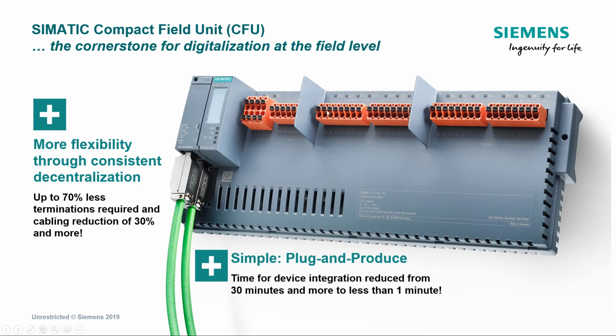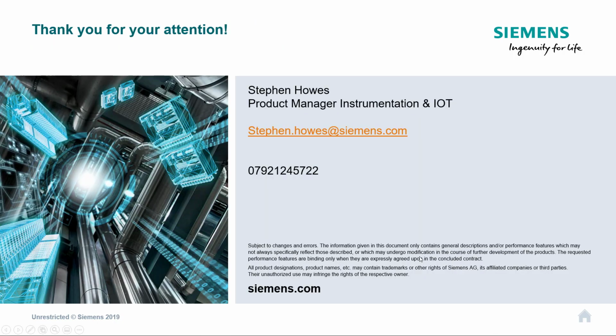So I'll do a video on this where I'll have a look at a network, the older style network and the Compact Field Unit, because when you're using PDM it speeds up the uploads and downloads for each instrument. So again, that could be a big saving. If you tie into that, if you're using Siemens instruments with the Quick Start Wizards that can help with commissioning, we can bundle all this together, and you've got some real big savings on using Profibus PA Compact Field Units. So that's me finished.